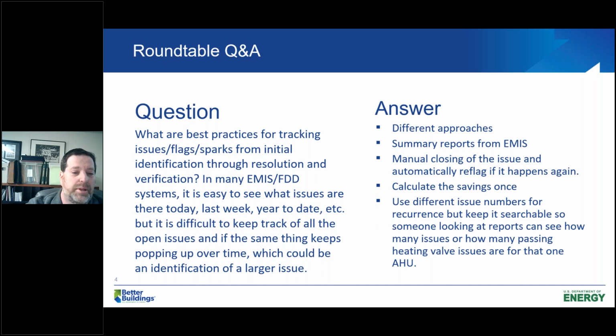When the work order is complete and verified, it should also be verified as closed, not just from the work order but also in the EMIS. It'll be closed by no longer seeing it flagging there. I like to wait for a little length of time, especially for something like an economizer that's only seasonal, since it may not be flagging, but I wouldn't close it out until you can see it under the right kind of weather to verify whether or not it's occurred.